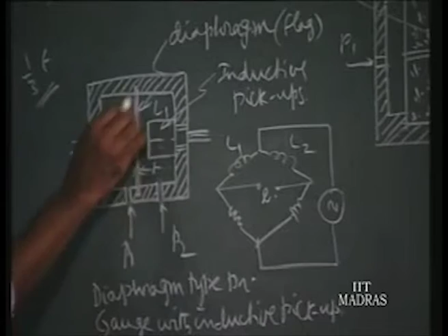The diaphragm is made up of a magnetic material. So when it moves nearer one of the inductive pickups, which is nothing but an inductive coil, the inductance of that will increase. So L1 will increase, and L2 will decrease to the same extent that L1 has increased from the original value. These two, L1 and L2, will form adjacent arms of an AC bridge.